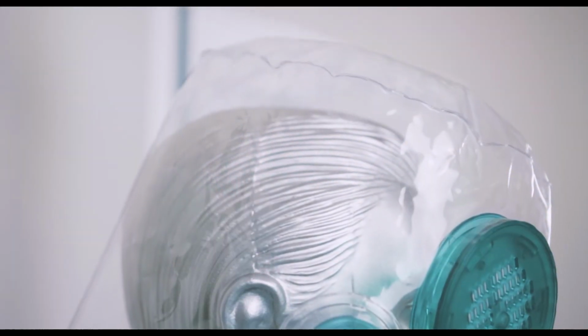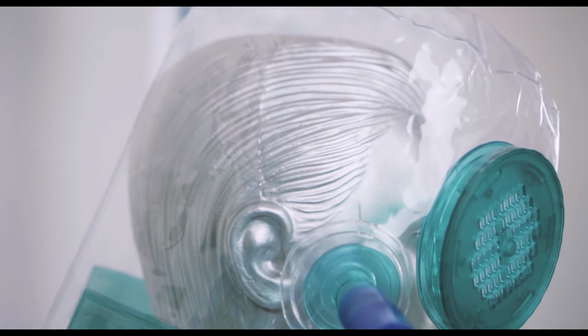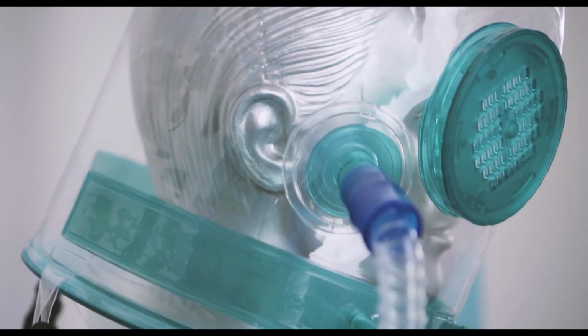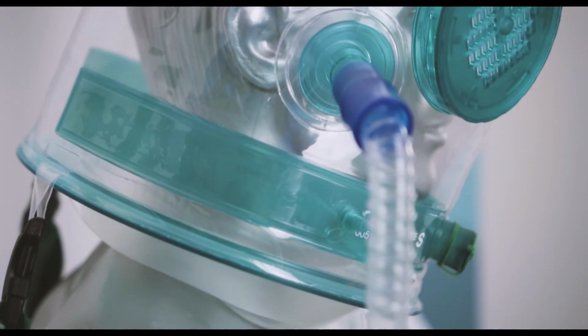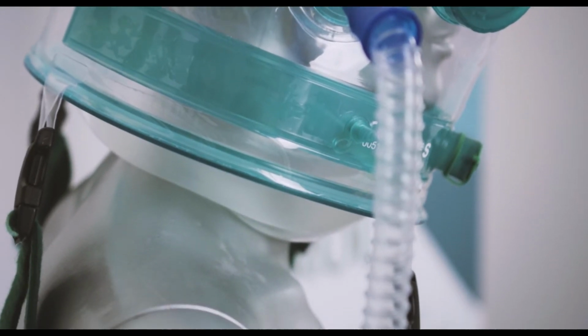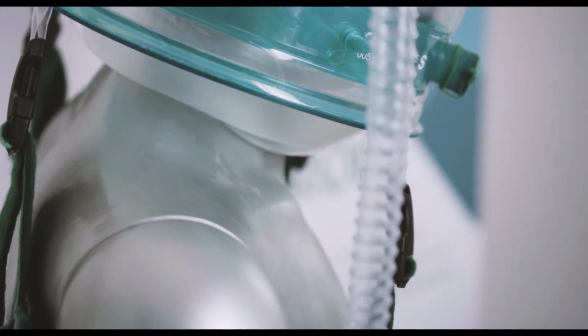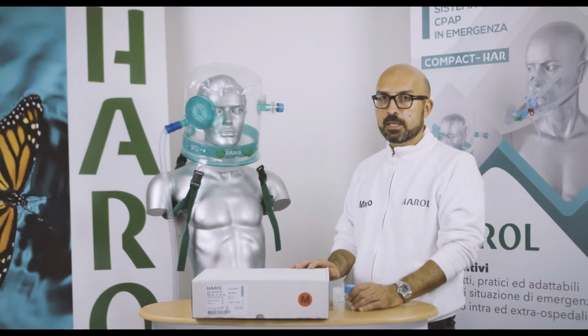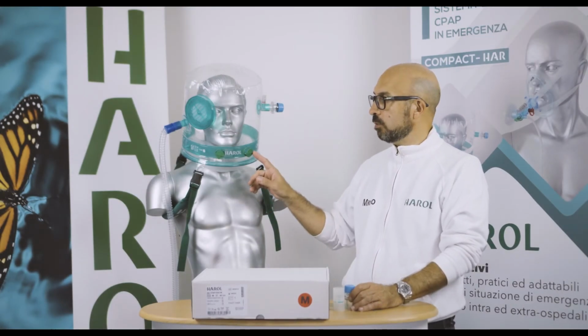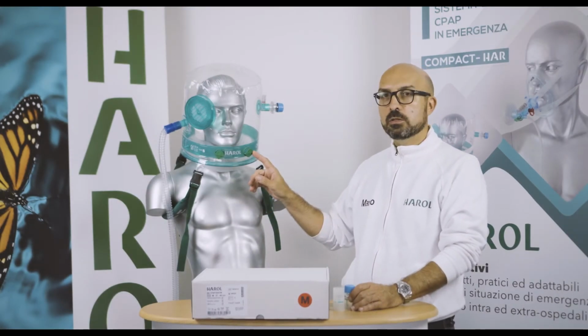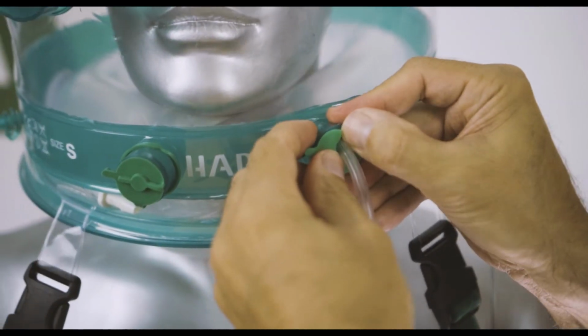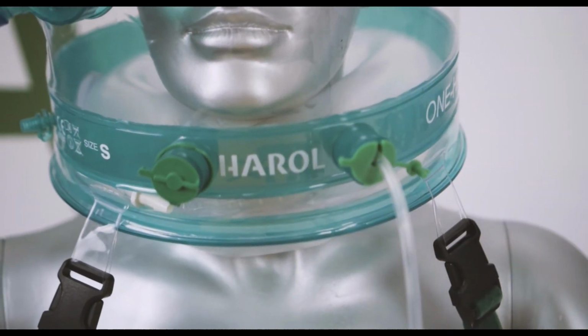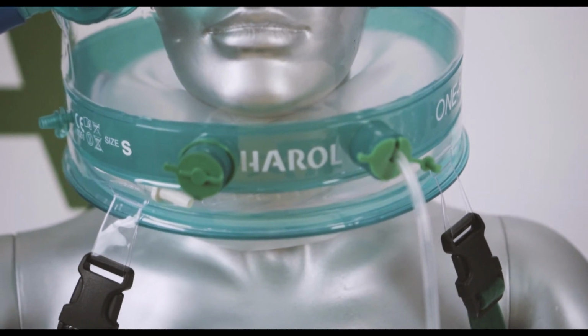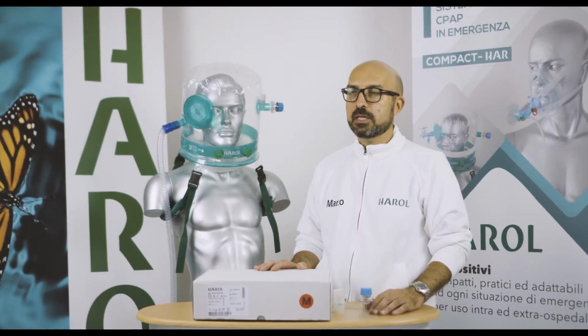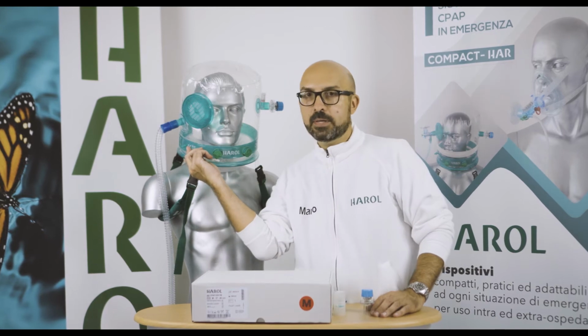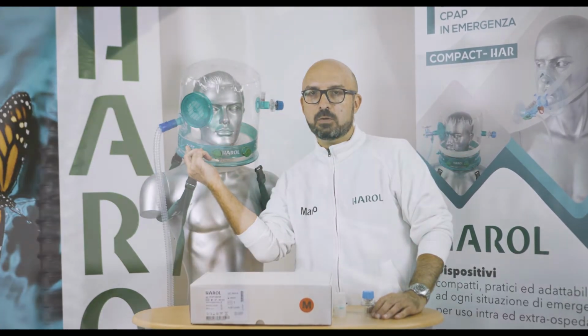A pocket on the inlet connection directs the flow tangentially to the inner surface, to reduce noise inside the helmet and to avoid air against the patient. On the lower part of the tent, there are two additional sealed accesses for the introduction of nasogastric tubes or straws for liquid feeding. On the band, you will also find a port for connecting an external manometer or a monitor to check the inside pressure.